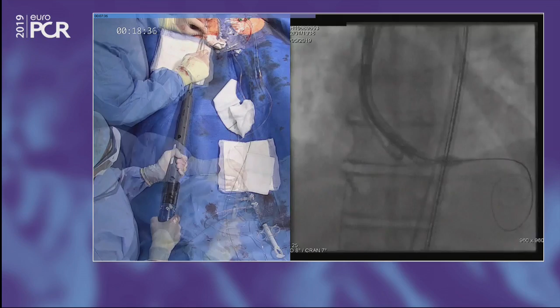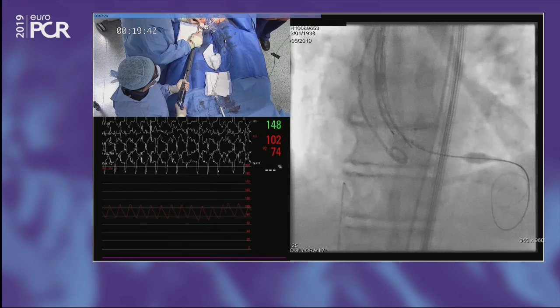We're going to carry on releasing this. And remember, it foreshortens from the bottom 4 millimeters, and it needs to lock, so that's good. We've got a bit of foreshortening to come at the bottom. We're at the annular plane. Valve is functioning at this point.